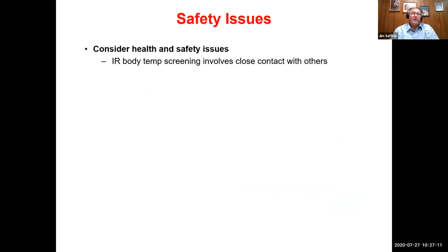When it comes to this application, one must consider safety issues and health issues. Infrared body temperature screening involves close contact with others. Now, as a thermal imager operator, you can operate remotely, but somebody, whether it is the infrared equipment operator or a second person, if you have a large group of people being screened with a steady flow of people, is going to be basically at arm's length when they use an infrared thermometer to confirm the body temperature of those testing positive.